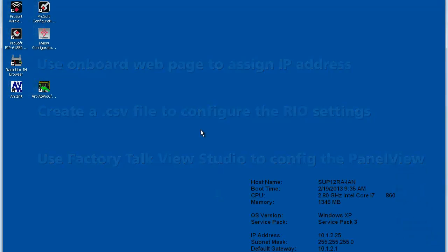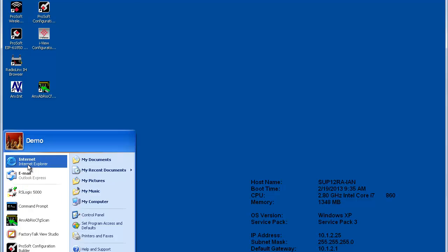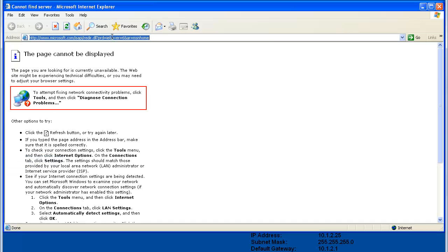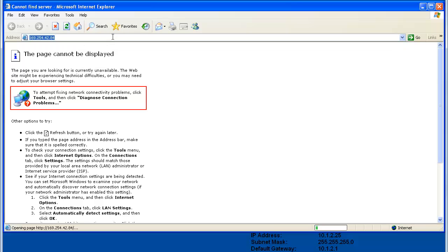To get started, I'll access the ANX2's onboard web interface where I can change the IP address and assign a new hostname. The ANX2 gateway is shipped with the link-local IP address of 169.254.42.84, which can be accessed regardless of what subnet your computer is using. I'll plug the ANX2 into a switch that my PC is plugged into as well, open a browser, and enter the module's link-local IP address.